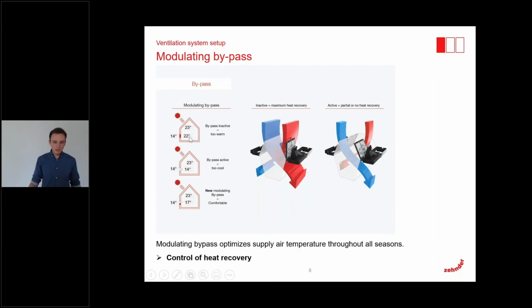You can see it on the left-hand side. This could occur, for example, in autumn in our region. So we have a sunny day, we have 14 degrees outside. Inside we have 23 degrees due to internal gains and also to solar gains, so it's a little bit too warm. We would like to have 21 degrees, for example. So if we now use the full heat recovery, we will take in the air at a temperature of 22 degrees because of the 90% efficiency.